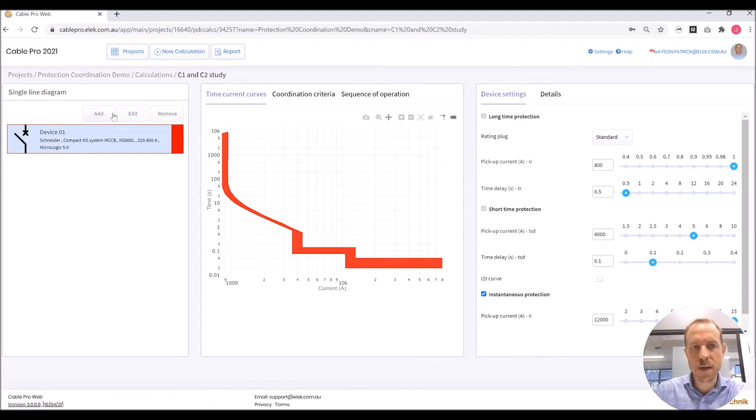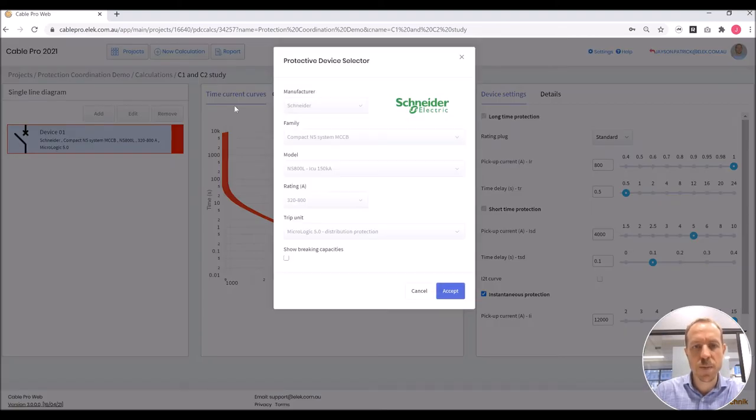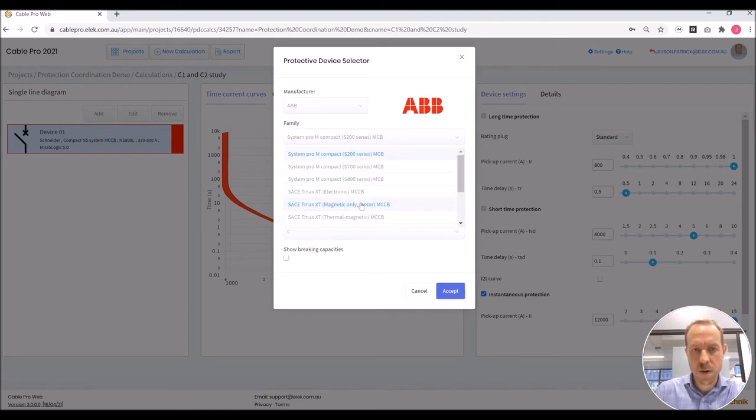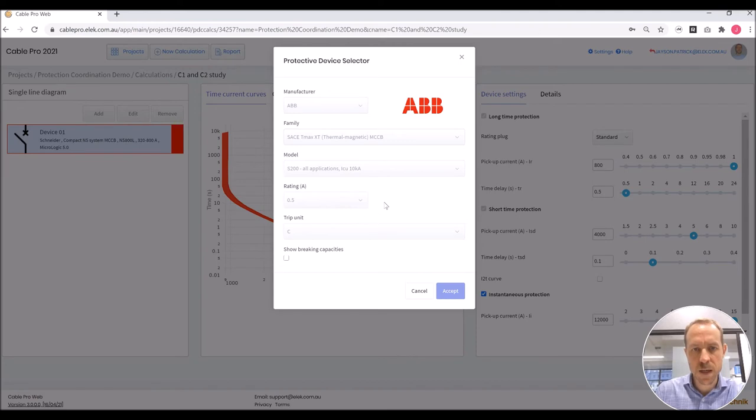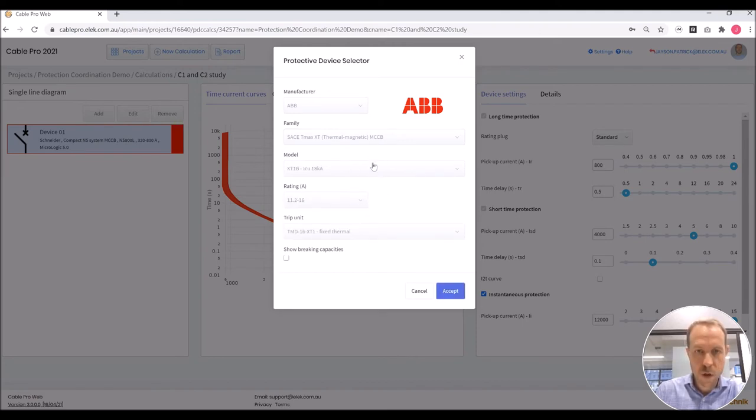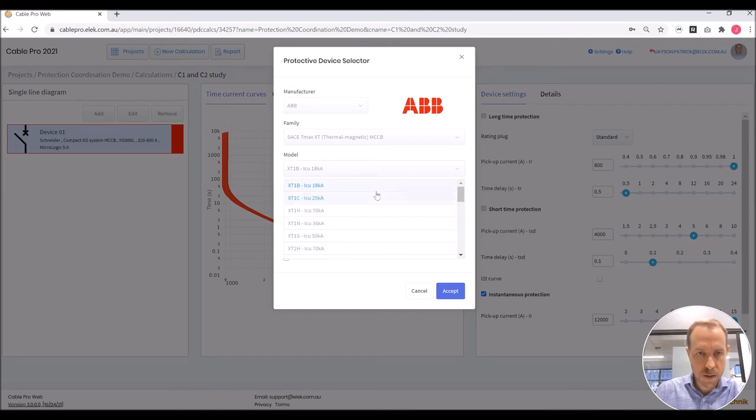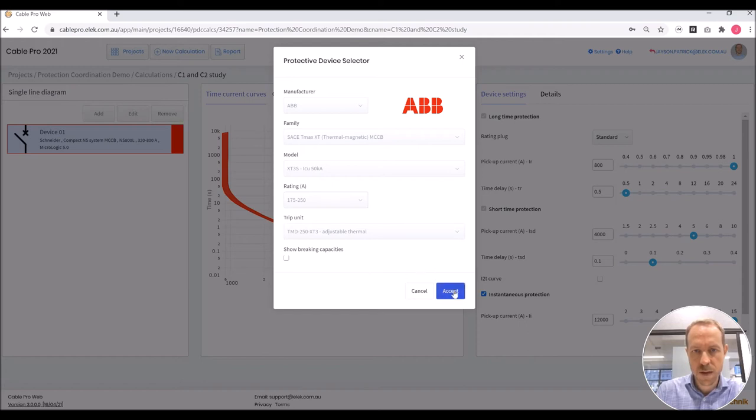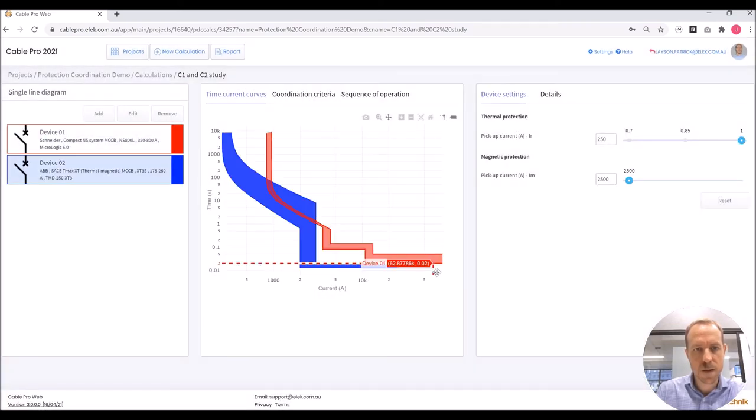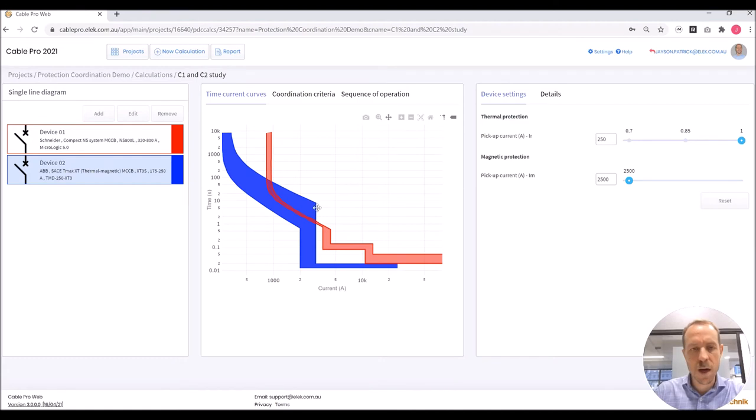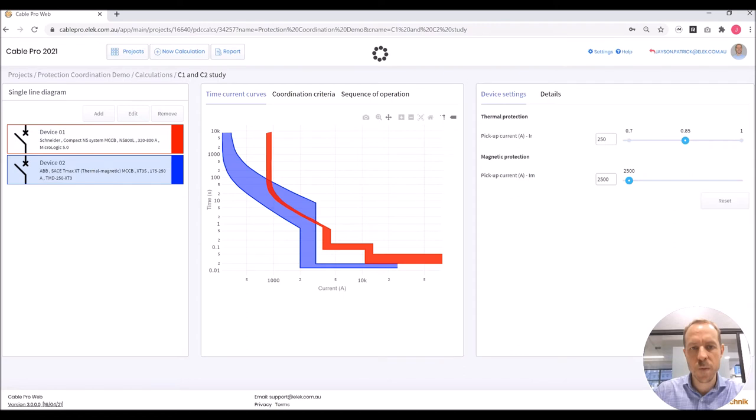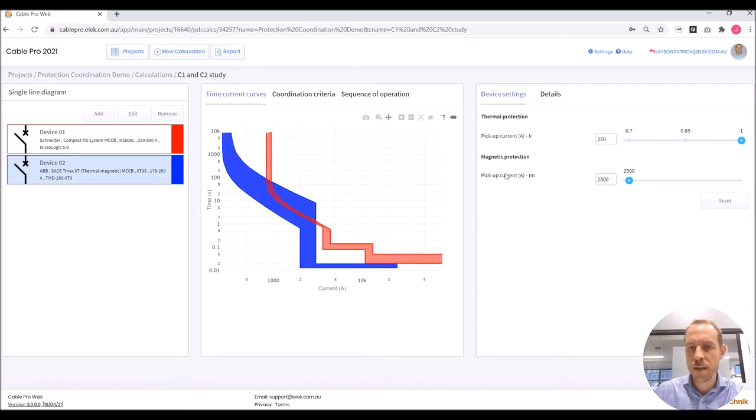Now I'm going to add the downstream breaker C2. That is an ABB thermal magnetic MCCB. The model is XT3S. The rating that we need is 250 amps. The trip unit is selected. Now we can see the time current curves of both devices. We can switch between them, they are highlighted in this plot, and the settings are shown over to the right for both devices.